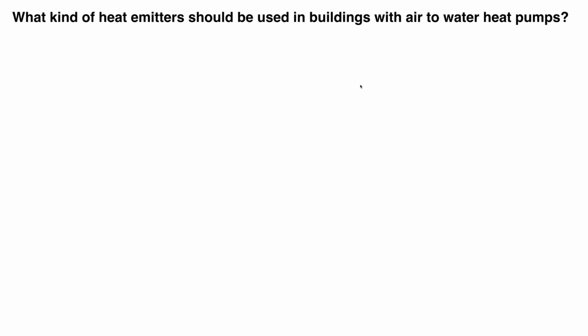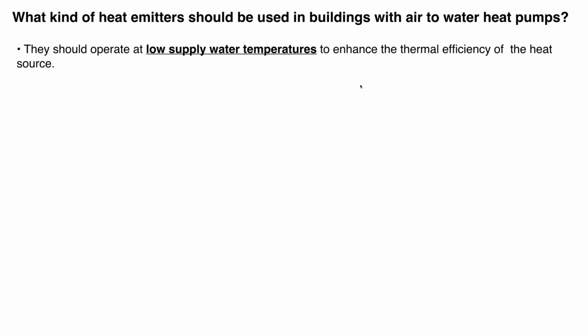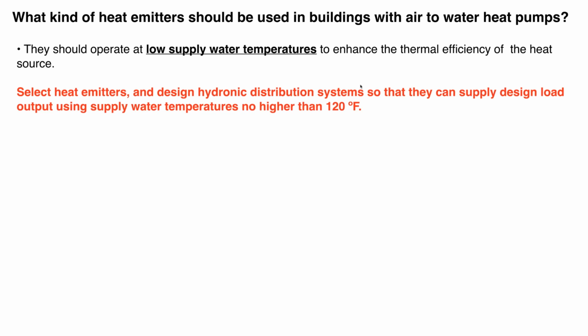Okay? Now, let's look at the heat emitters, okay? Again, I think we've probably answered this question multiple times, but I'm going to emphasize it again. We want low water temperatures to keep that heat pump operating at its peak capacity. And I'm going to suggest, and this is not an ASHRAE standard, it's not a code requirement that I'm aware of, but it's a guideline that I've used for many years when we design hydronic systems. And this is across the board now, regardless of what the heat source is. We like to design hydronic heating systems so that at design load conditions, we don't need a water temperature over 120 degrees Fahrenheit, okay? Even lower if possible, and certainly with some radiant panels that we're going to look at, we can get that down another 20 degrees.